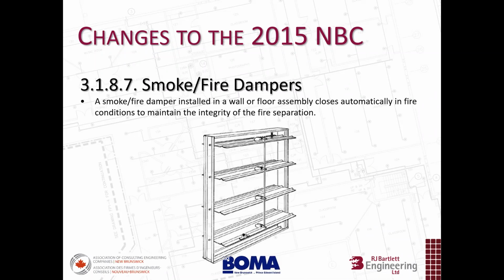A story that I heard, and one of the driving forces behind including these combination smoke dampers into the building code, was an instance where there was a smoldering fire, I believe, in a nursing home in the garbage room. That smoldering fire did not get hot enough to activate the sprinkler protection and was able to allow smoke to migrate through the duct system and distribute throughout the building, and resulted in some casualties because of that. So it's for those examples. The other factor is, as many know, the leading cause of death in fires is not actually direct exposure to fire, but the inhalation of smoke. So the idea behind these smoke dampers is to really reduce the amount of smoke propagation through a building.